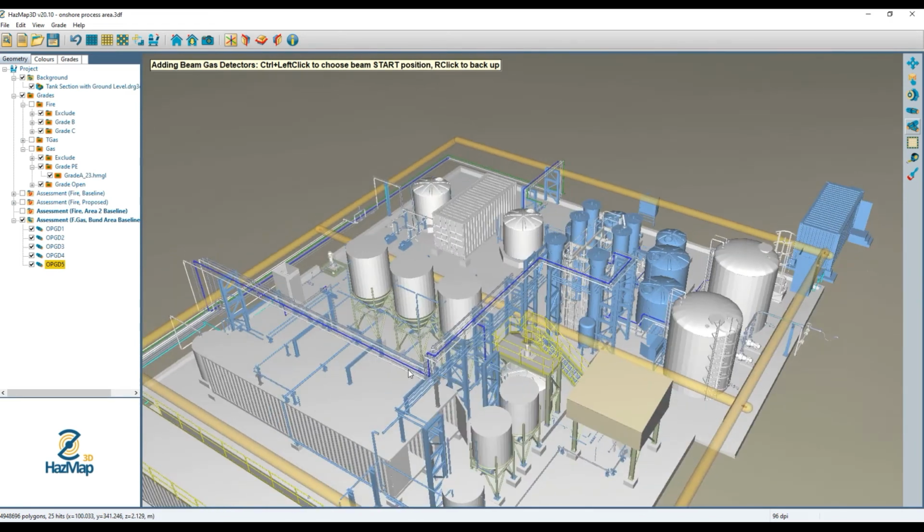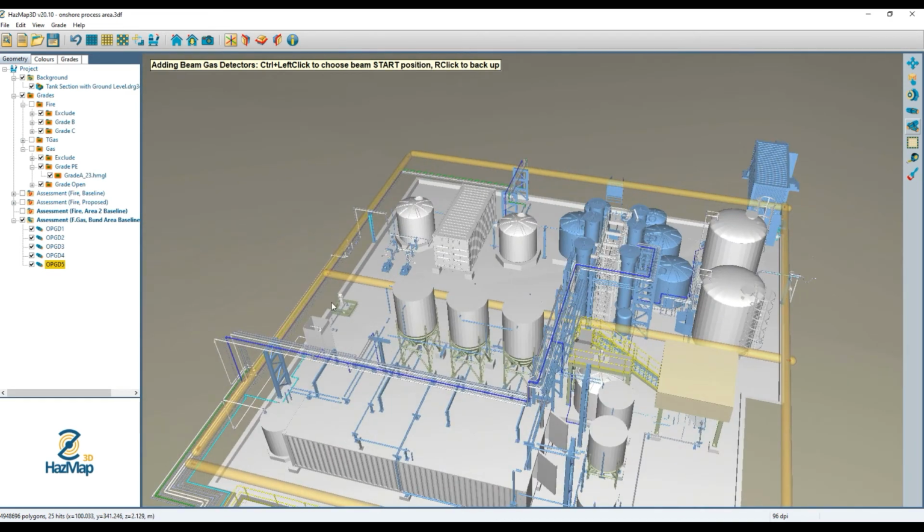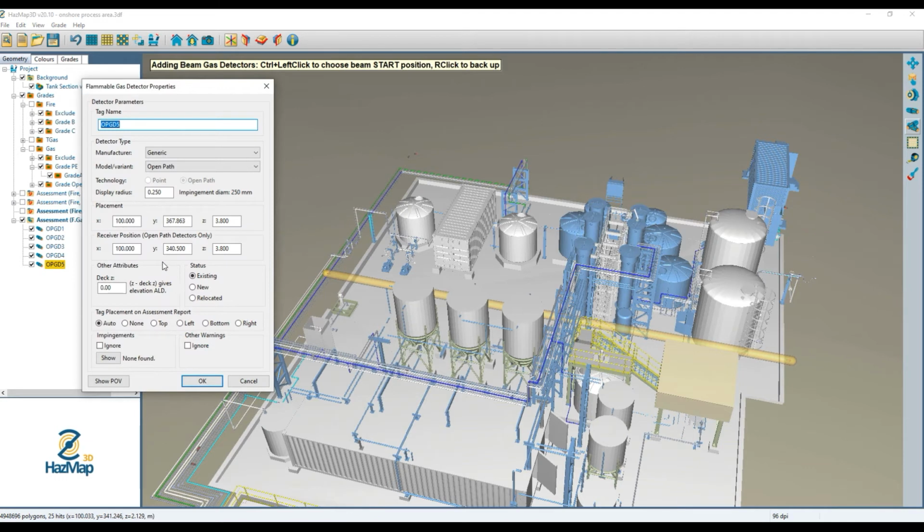And the main challenge you're going to want to avoid here is that when you install these, you don't want the detectors mounted in such a way that these posts are going to block that beam path. And if I want to be a little bit conservative about how I handle that, I can always change this Y coordinate to 1 and inset that a little bit, and take this in a little bit to say 6.5.